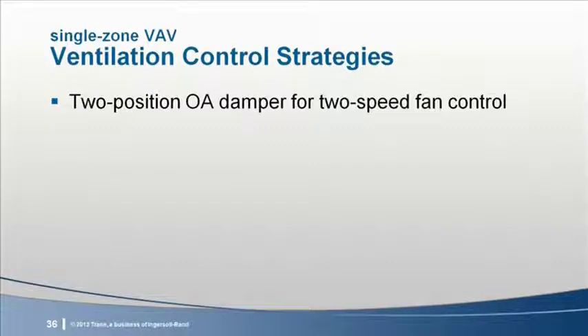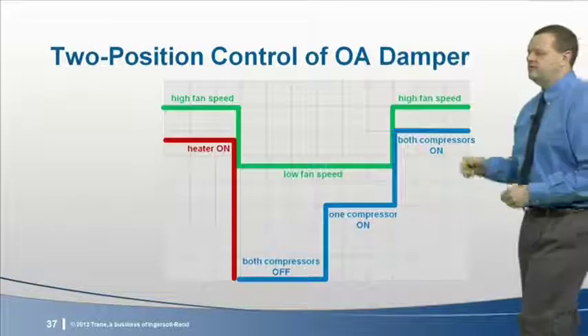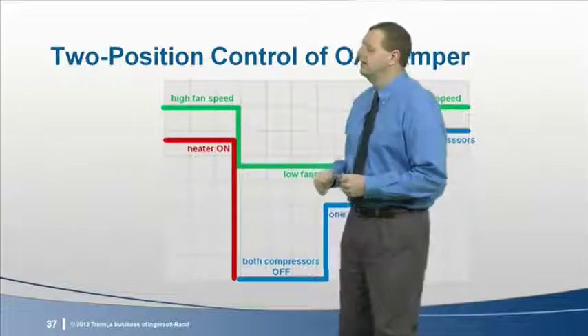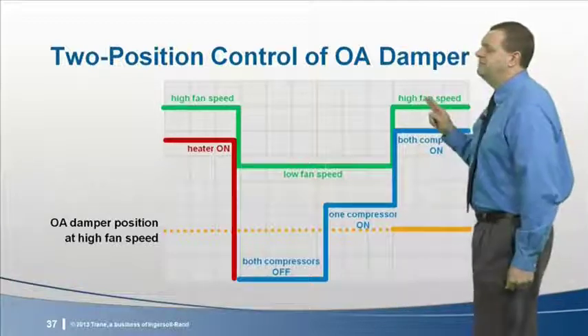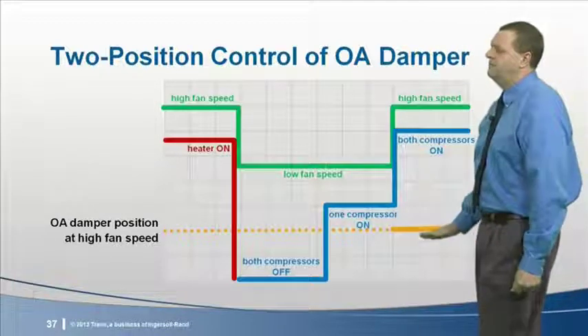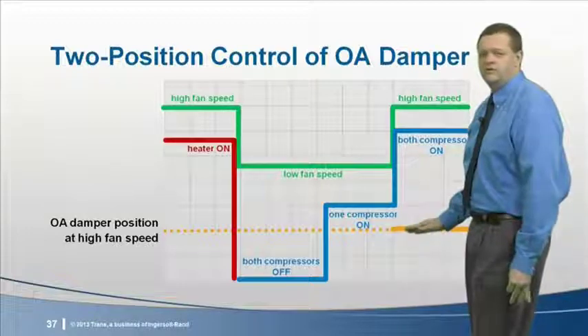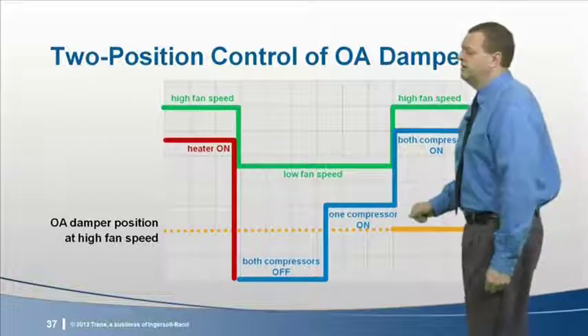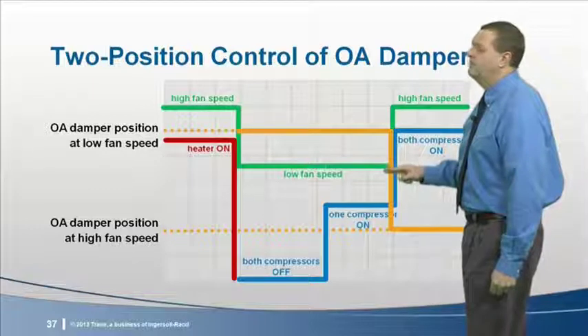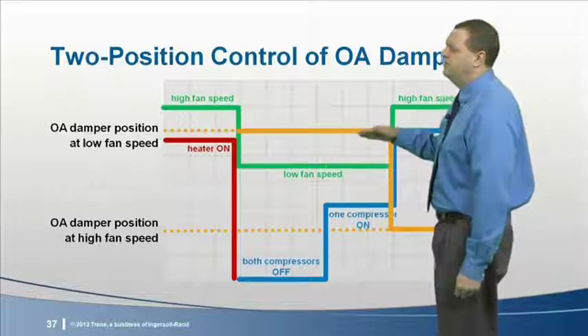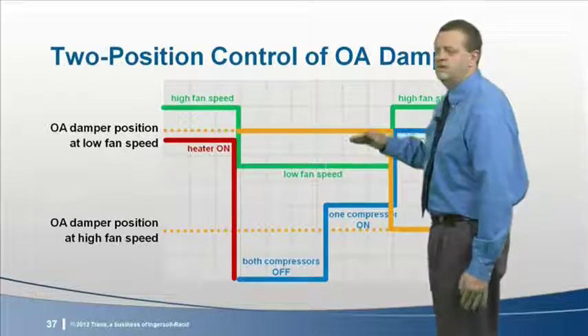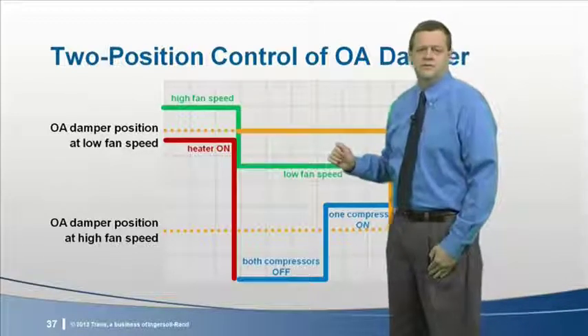I'll start with those systems that use a two-speed fan. This one's pretty simple in that you just need two position set points to control the outdoor air damper. Here again is the example control sequence for a two-speed fan system. When the fan is operated at high speed, the outdoor air damper position is set to bring in the quantity of outdoor air required by code. Then when the controller switches to operate the fan at low speed, the damper is adjusted to a more open position in order to bring in the same CFM of outdoor air.